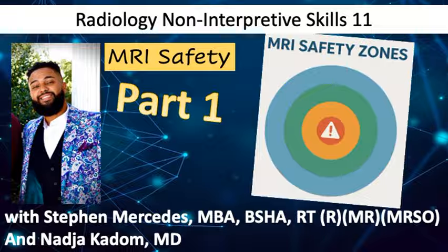Definitely. And then going back to the tethering that we have in zone 3 with the phones and the people avoiding putting them in their pockets, we have tethering inside of zone 4. We have plastic chains and ropes tied to the wall and tied to the machine so that when it's fully extended, it really only goes as far as that 5 Gauss line. Obviously, human error can slip into that and people can unloop it or do something like that. But again, we go through all these measures to try to avoid that from happening.